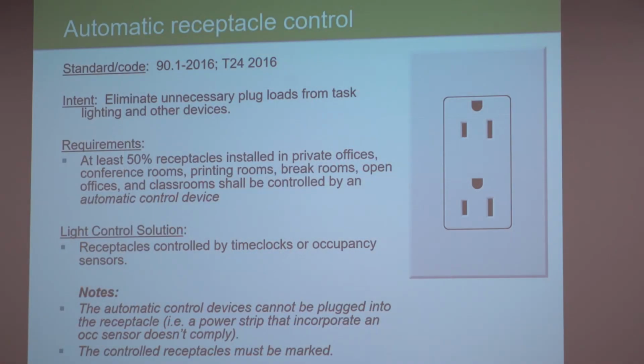Okay, receptacle control you don't have to worry about for Pennsylvania because it's not in IECC. It keeps failing to make it in the IECC energy code, all right? But just say if you're going to do an ASHRAE project, especially for a LEED project, for example, these spaces, break rooms, open offices, conference rooms, private offices, and classrooms, half of the receptacles in those spaces have to be automatically controlled. Meaning when the space is vacant, those receptacles will shut off the power to anything plugged into those receptacles. Okay?